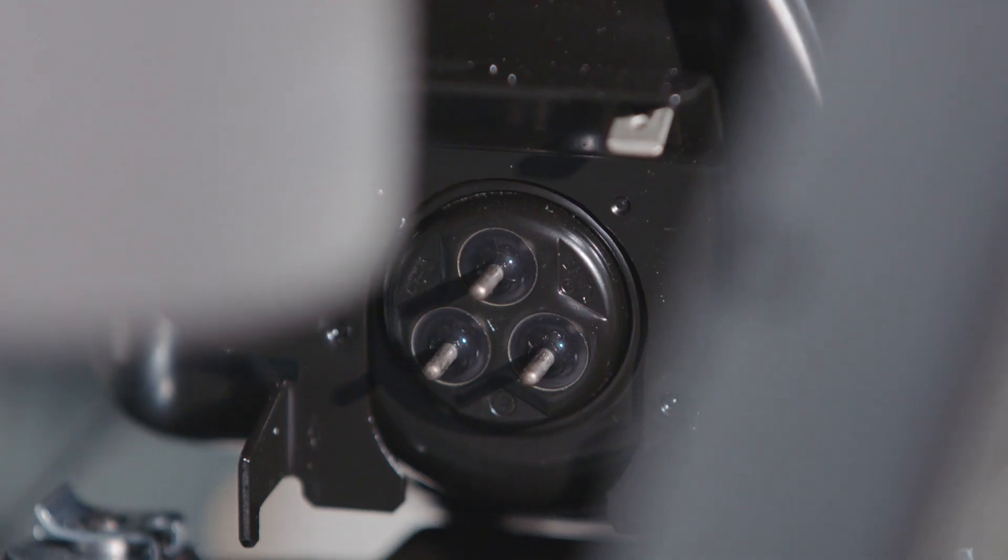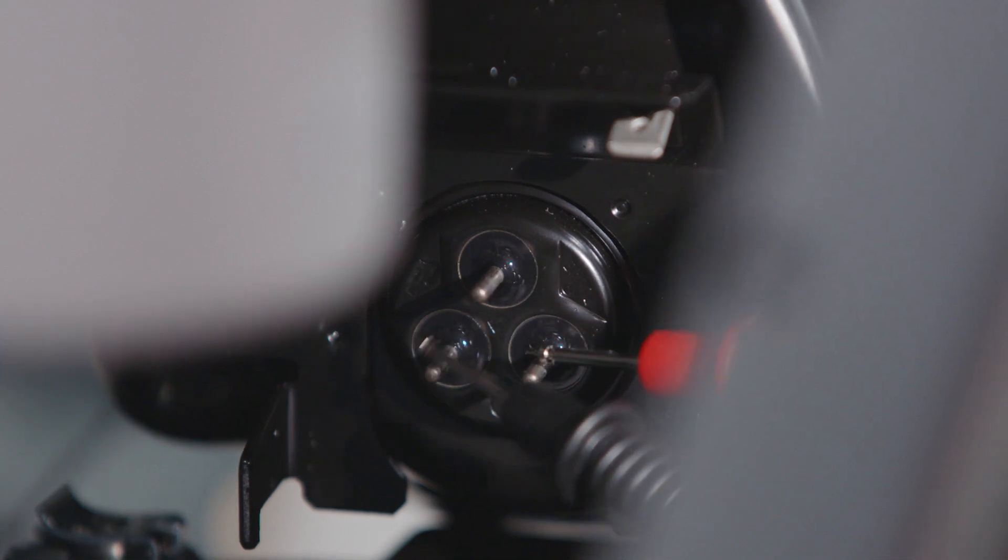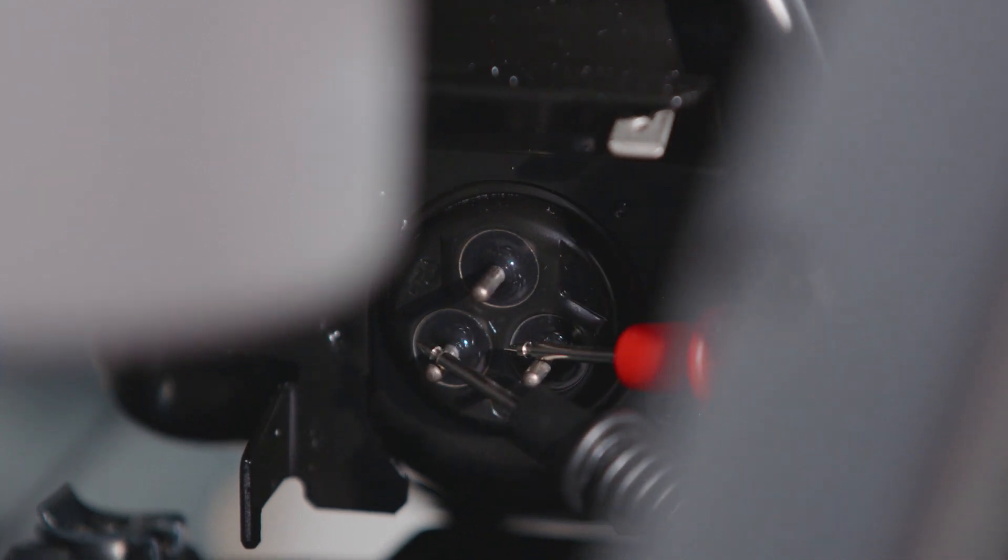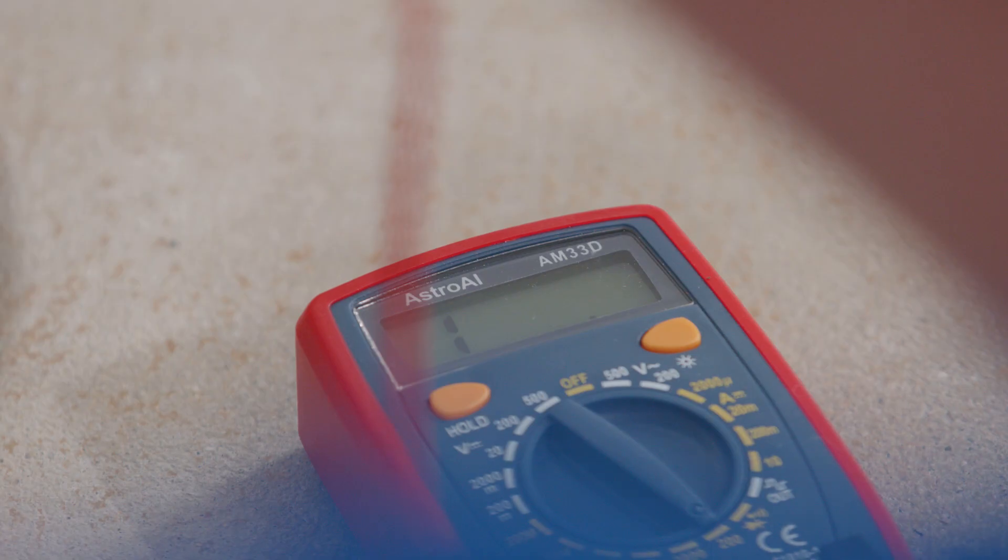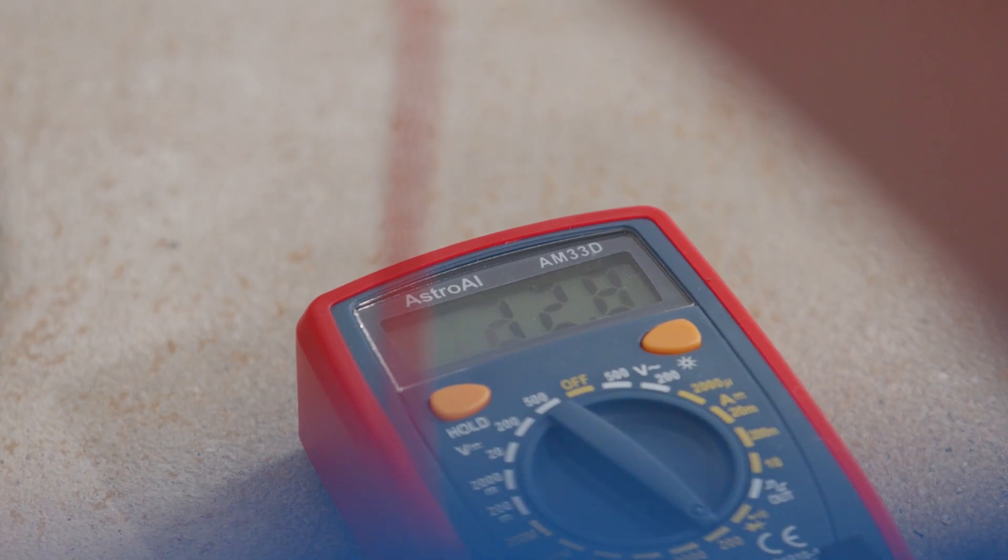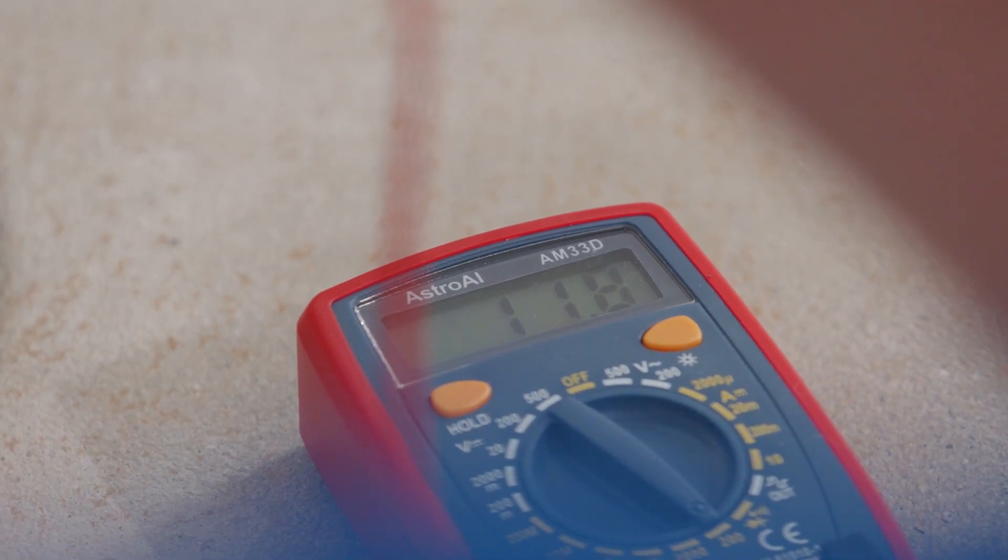Now place the red electrical probe to the run coil at the bottom right, while placing the black electrical probe to the start coil at the bottom left. Check the reading on the multimeter and write down the third reading.